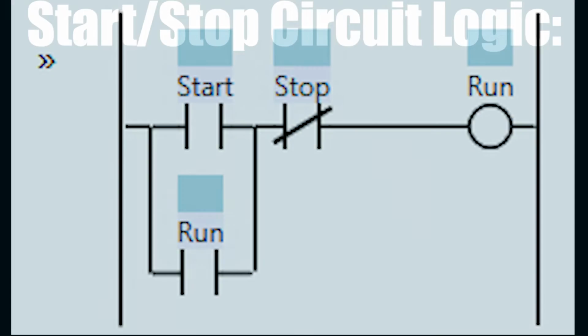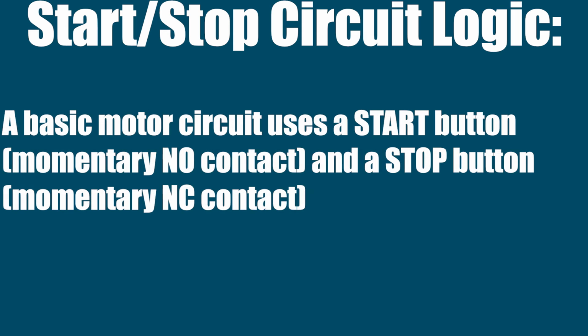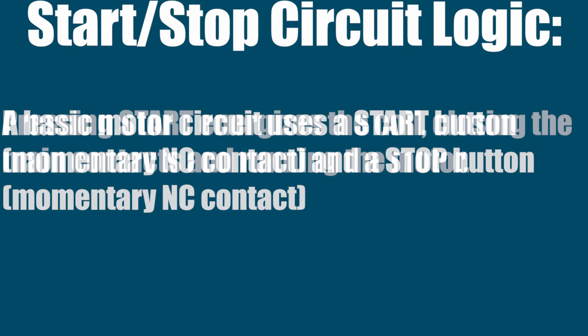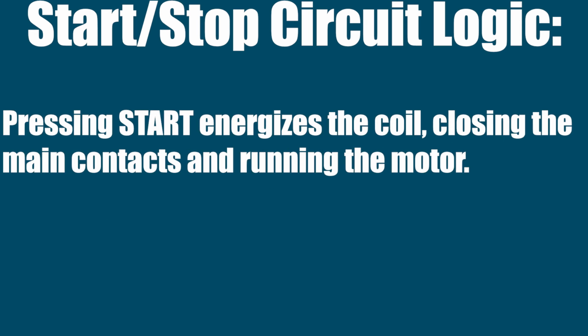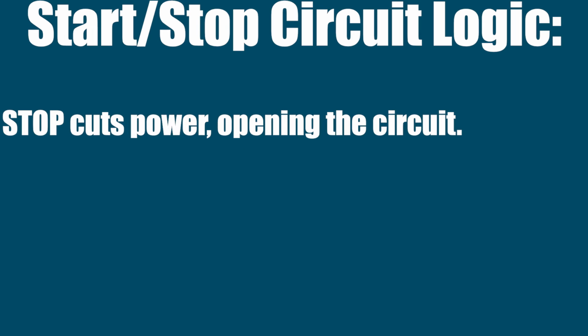First up, control circuits. This is the brain of your motor starter. Here's what makes it work. There's a start-stop circuit logic. So a basic motor circuit's going to use a start button for momentary, normally open contact, and a stop button for momentary, normally closed contact. Pressing start energizes the coil, closing the main contacts and running the motor. Stop cuts power, opening the circuit.